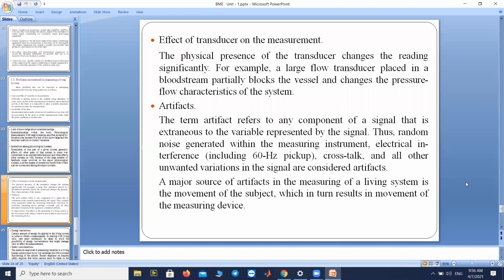Effect of the transducer is another difficulty. The physical presence of the transducer may lead to inaccuracy in the measurement. For example, a large flow transducer placed in a bloodstream. If we want to measure the blood flow in a blood vessel, and we cut the blood vessel and keep the transducer, what happens? We ourselves are changing the flow of the blood by placing the transducer before taking the measurements. That will definitely cause inaccuracy of the measurement. It will change the pressure of the blood flow. So a flow transducer placed in a bloodstream blocks the vessel and changes the pressure flow characteristics of the system.